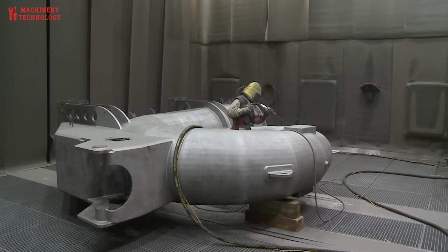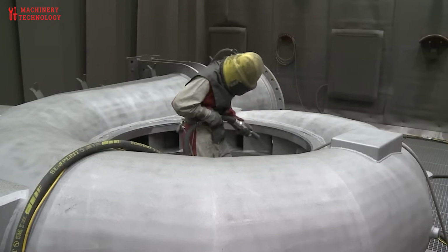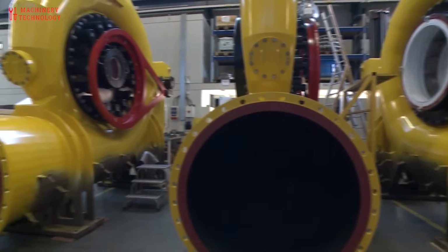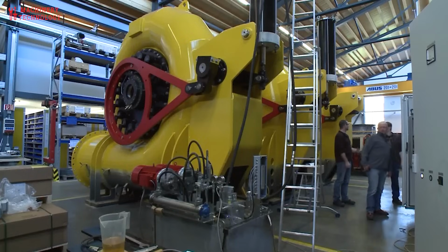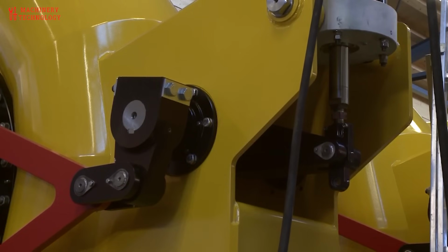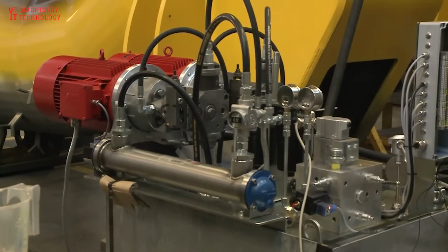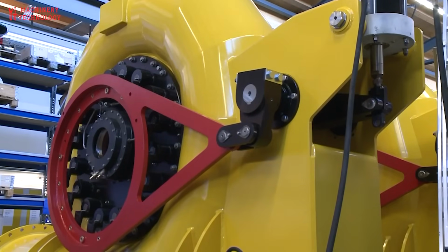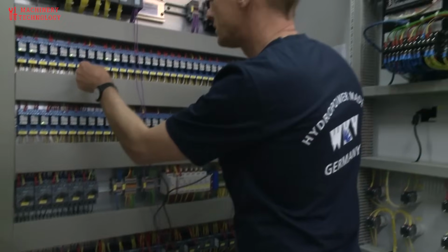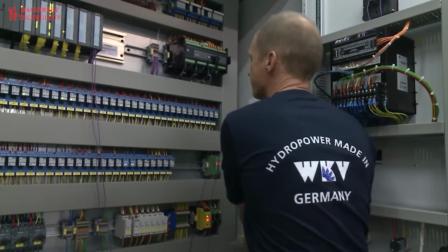If the electric load on the turbine changes, its power output must be rapidly adjusted to match the demand. This requires a change in the water flow rate to keep the generator's speed constant. The flow rate through each nozzle is controlled by the centrally located, carefully shaped spear or needle that slides forward or backward as controlled by the hydraulic servo motor. Proper needle design ensures that the velocity of the water leaving the nozzle remains essentially the same irrespective of the opening, assuring nearly constant efficiency over much of the operating range.